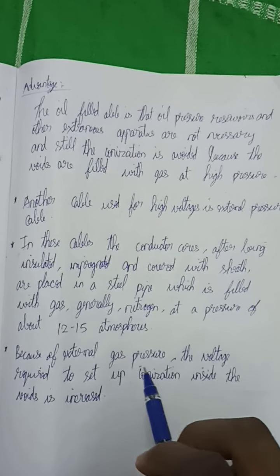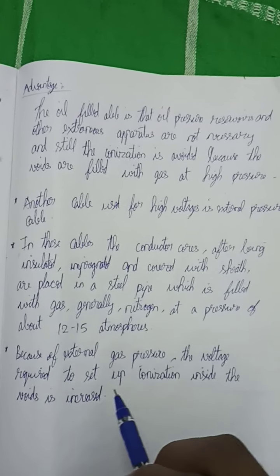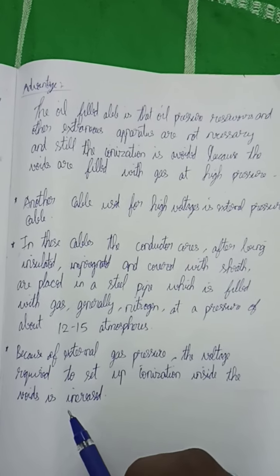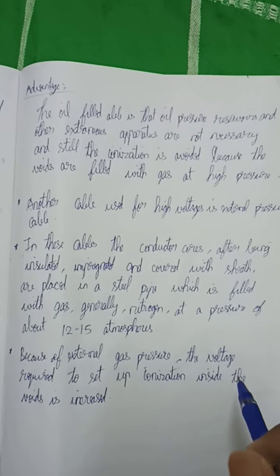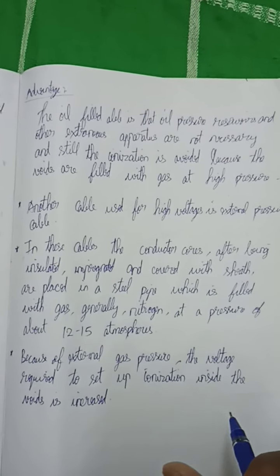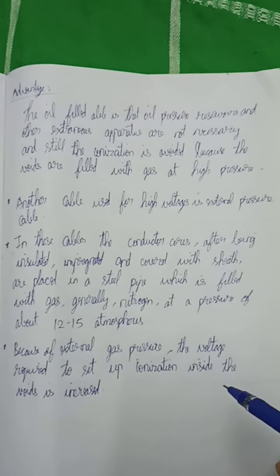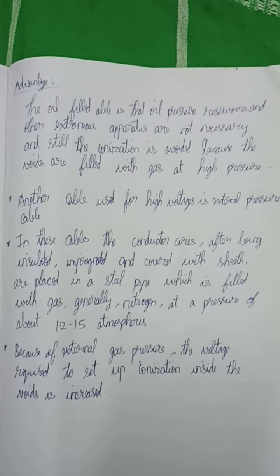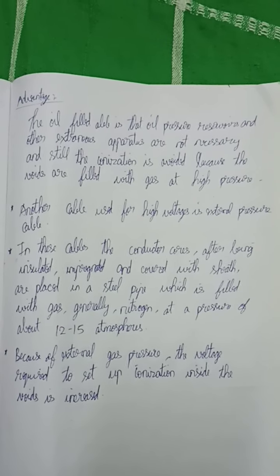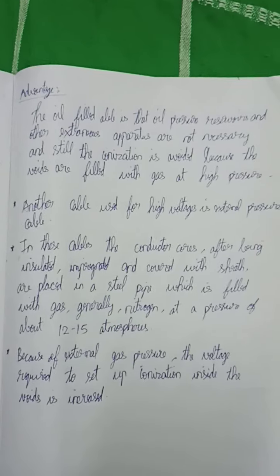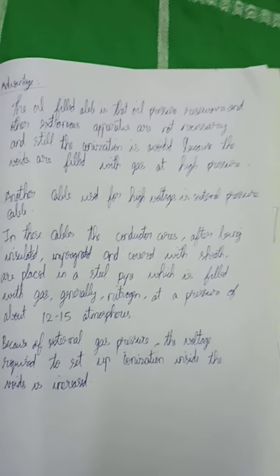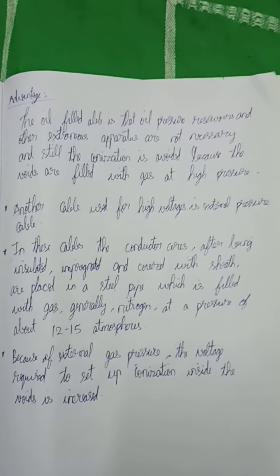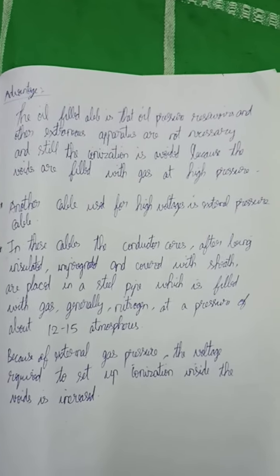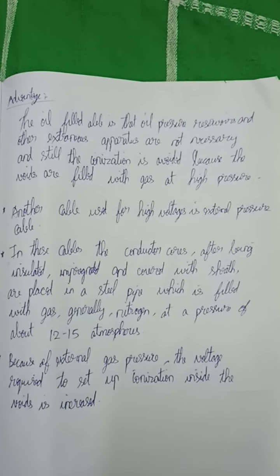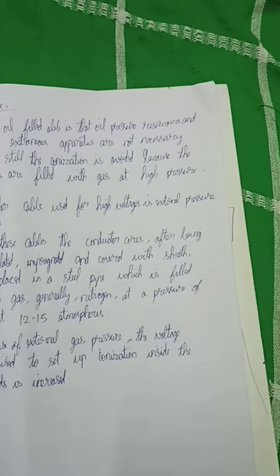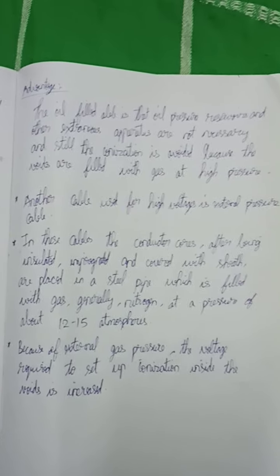Because of the external gas pressure, the voltage required to set up ionization inside the voids is increased. These are the points of external pressure cables. The two types of pressurized cables are oil filled cables and gas filled cables. We saw the advantages of both oil filled cables and gas filled cables. These are the pressurized underground cables. Okay, thank you.